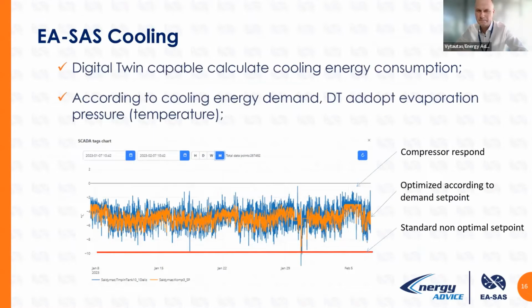And what we delivered for systems like ammonia, CO2, and freon, where the agent directly acts in the cooling process, is this: we made a digital twin, a full model of the compressor, the evaporation side, and then the full compressor station, including consumer sites, using only data that the PLC or SCADA OPC delivered to us. We are capable of calculating the cooling energy consumption at that moment. And if we know that, we can add the metered electricity value and calculate the coefficient of performance very well.